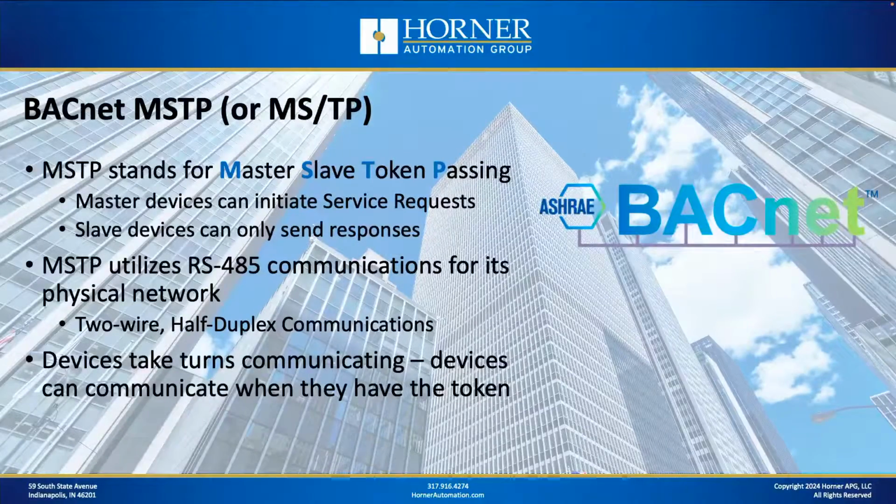So over MSTP, only one device can transmit at a time. So how do you decide who gets to transmit when? Well, the devices are going to take turns communicating and transmitting based on a token. So whatever device has the token, that device gets to transmit at that point. And then when it's done transmitting, it passes the token on to the next device.